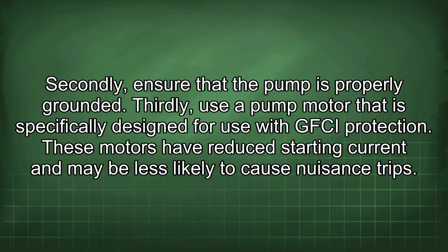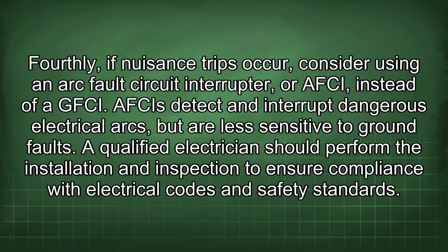I recommend that you firstly install a proper GFCI circuit breaker or outlet for the jacuzzi pump. Secondly, ensure that the pump is properly grounded. Thirdly, use a pump motor that is specifically designed for use with GFCI protection. These motors have reduced starting current and may be less likely to cause nuisance trips. Fourthly, if nuisance trips occur, consider using an arc fault circuit interrupter, or AFCI, instead of a GFCI. AFCIs detect and interrupt dangerous electrical arcs, but are less sensitive to ground faults.